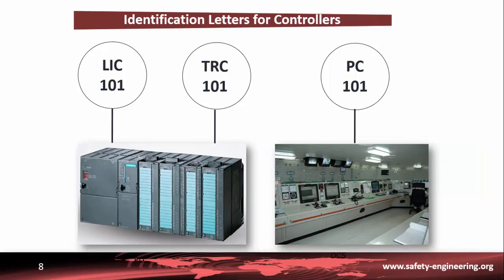Sometimes controllers have a recorder to save data in order to inform technicians or engineers. To indicate this feature, the letter R is placed in the second or third position. A recorder is a device that records the output of measurement devices. Many process manufacturers are required by law to provide a process history to regulatory agencies. Manufacturers use recorders to help meet these regulatory requirements, and also to collect data for trend analysis. By recording readings of critical measurement points and comparing those readings over time with process results, the process can be improved.